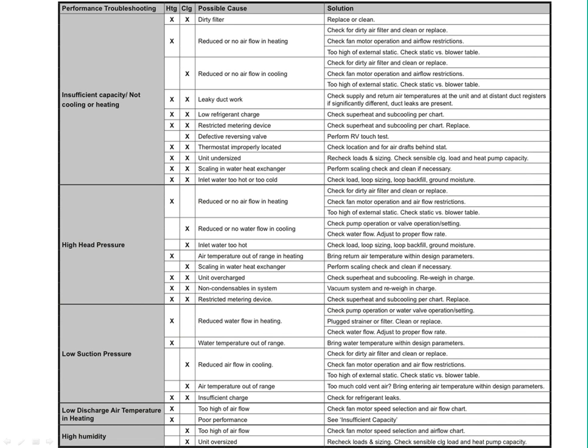So, insufficient capacity, not cooling or heating. Gosh, I see that all the time. First thing you want to do is make sure that that unit is delivering all the goods. So that heat of extraction, heat of rejection is always first and foremost. If that loop is performing, if the heat pump is producing all the BTU, either rejecting or extracting, heating or cooling, and that CFM is delivering out in the space, well, it can only be a couple things left.